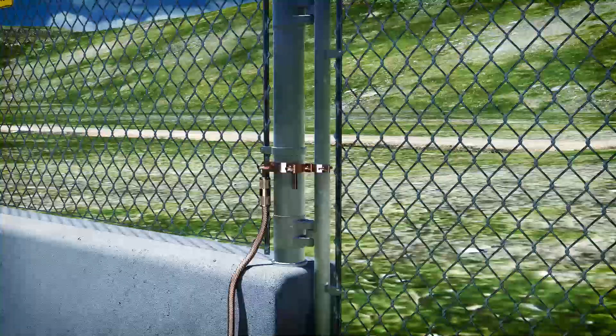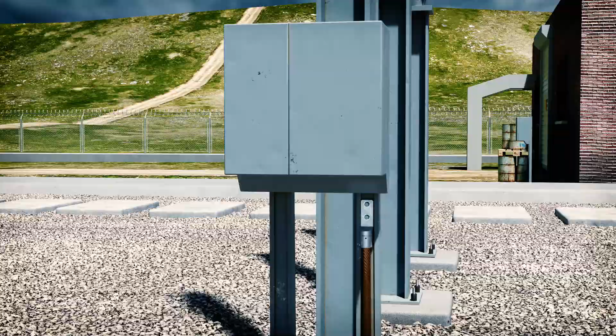All substations are required to be grounded. Every piece of equipment, including the perimeter fencing, is connected to an underground grid to provide safety to personnel and equipment. In the event of an electrical fault, the electricity will safely discharge into the ground grid.